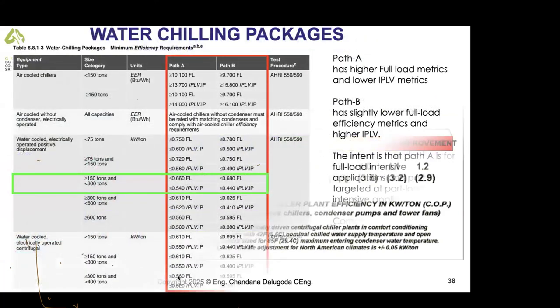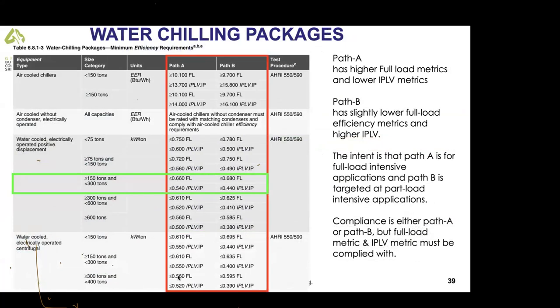This is a page from 90.1, on how to select a chiller complying with energy efficiency. These are minimum efficiency requirements. For instance, a water-cooled chiller, 150 tons and 300 tons. Full load efficiency is 0.660 kilowatt per ton, and part load efficiency is 0.540 kilowatt per ton. Path A means full load metrics. If the chiller is running at part load continuously in that application, then path B applies, 0.68 kilowatt per ton and 0.44 integrated part load value. So we have to comply when selecting chillers.